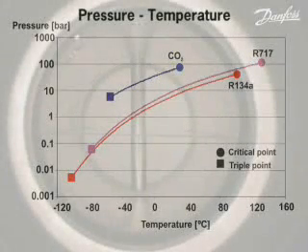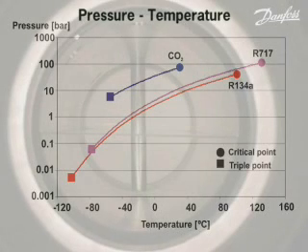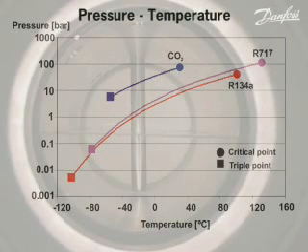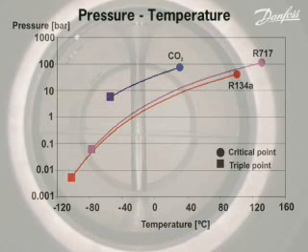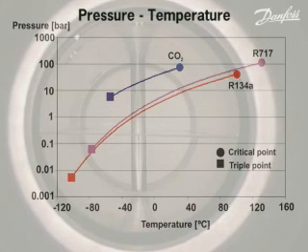When compared with commonly used refrigerants R134A and R717, CO2 has some unique characteristics. It operates at a much higher pressure but across a narrower temperature range than both R134A and R717. The pressure at the triple point is high and the temperature at the critical point is low. These facts must be taken into account when CO2 is utilized as a refrigerant.